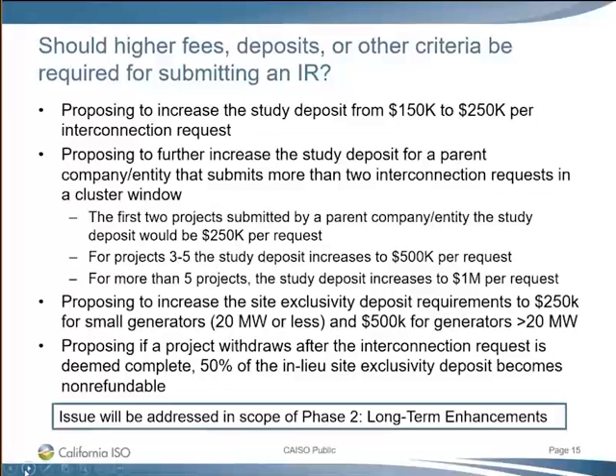We're also proposing to increase the site exclusivity deposit requirements, or in-lieu-of-site-exclusivity deposit, for small generators of 20 megawatts or less from the current $100,000 to $250,000. For large projects over 20 megawatts, it will increase to $500,000. Associated with that, we're proposing that if an interconnection project withdraws after the interconnection request is deemed complete, 50% of the in-lieu-of-site-exclusivity deposit would become non-refundable.